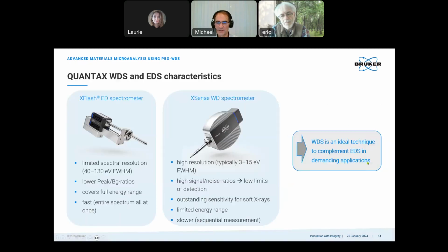To conclude this, here's an overview of the characteristics, the advantages and disadvantages of EDS and WDS. The EDS has a somewhat limited spectral resolution and lower peak to background ratios than WDS. On the other hand, it covers the entire energy range, and it's fast since we acquire the entire spectrum just at once. On the other hand, the WDS shows much higher spectral resolution, up to 20 times higher.